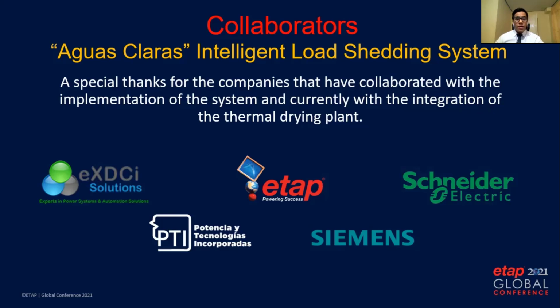ETAP is the provider of the ILS servers, workstations, historian server, and analysis software. They have designed the ILS system logic and all the ETAP real-time software configuration on the machines. PTI has collaborated in the design of new HMIs for the system, the integration of the signals from the thermal drying plant, and the support on site for test and acceptance.